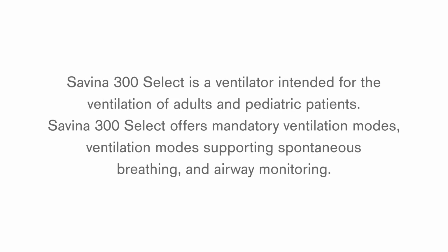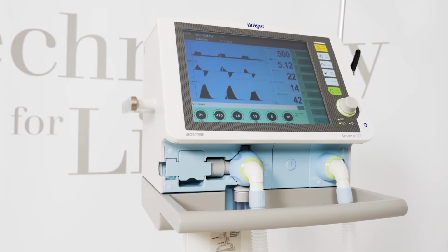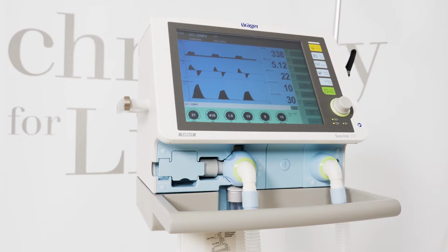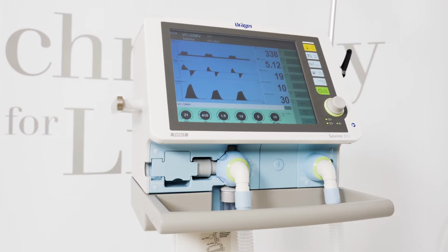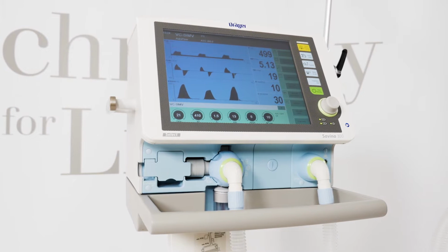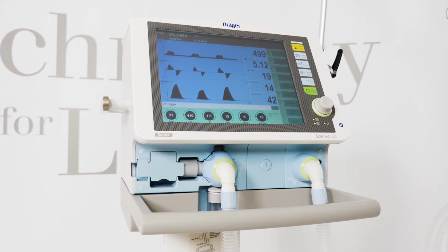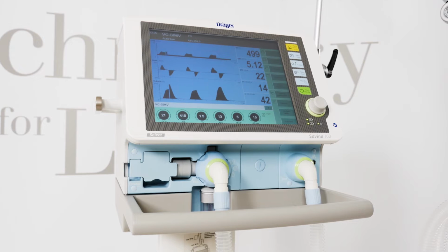In this chapter, you will see how to prepare Savina 300 Select for its use on the patient. Before the Savina 300 Select is connected to a patient, the device should be cleaned in accordance with the hospital hygiene regulations and the corresponding instructions for use. Savina 300 Select can be used for the ventilation of intubated patients in application mode tube, for non-invasive ventilation in the application mode NIV, and for O2 therapy.